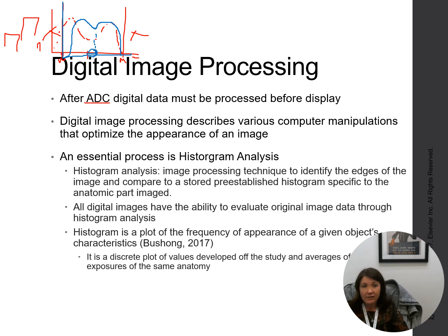The difference between the two, the lookup table S-average and the raw data S-average, is going to show the deviation index from the perfect target exposure. So if my lookup table S-average, my perfect target exposure, was, let's say on our system, 800, and this one was 600, my deviation index would be 200. Having to move from 600 to 800 was a deviation of 200.